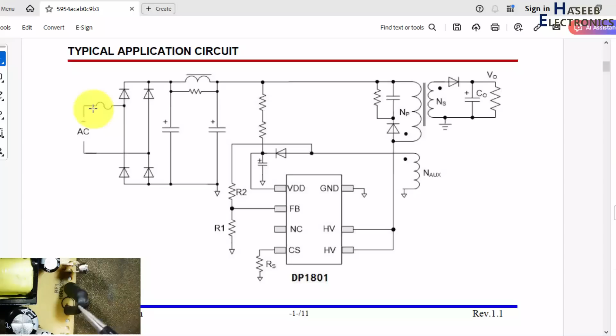When we are testing, if we don't find voltage at the input terminals - this one and this one - the second step is to check AC voltage at these 2 points. If we cannot find voltage here, then we can remove the AC input voltage and check continuity between these 2 points across this fuse.